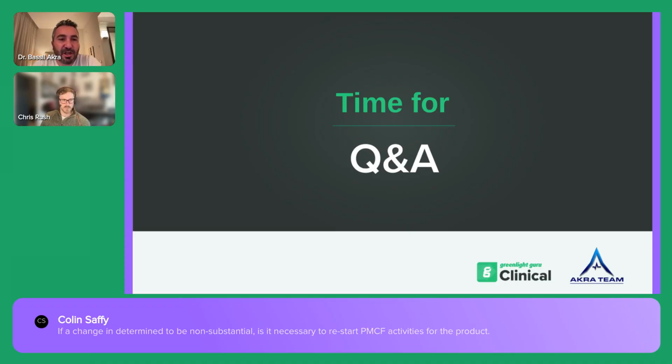Because a non-substantial change could be that you did a correction in the IFU, which was a typo. So do you need to repeat the PMCF for a typo? It depends on what that change is. But I think in general, no, you don't need to do that.